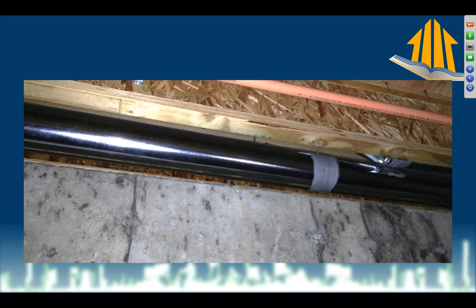And the secret is that no one's going to say anything until the homeowner moves in and finds out that that duct doesn't blow warm air, because it's losing all of its heat straight through this uninsulated bit at the outside. That's totally, totally avoidable.